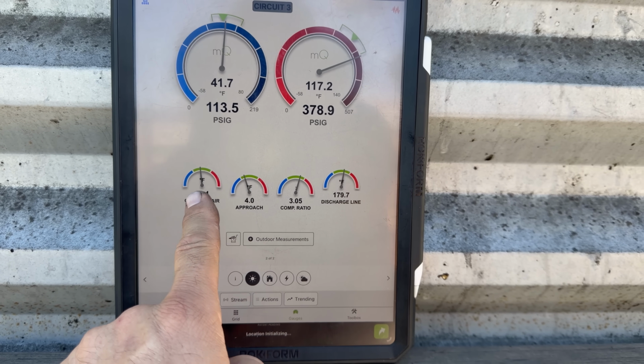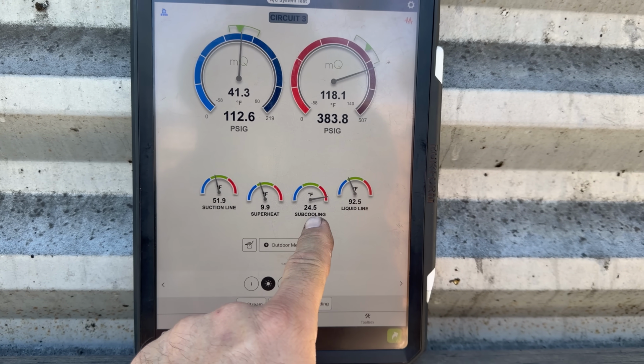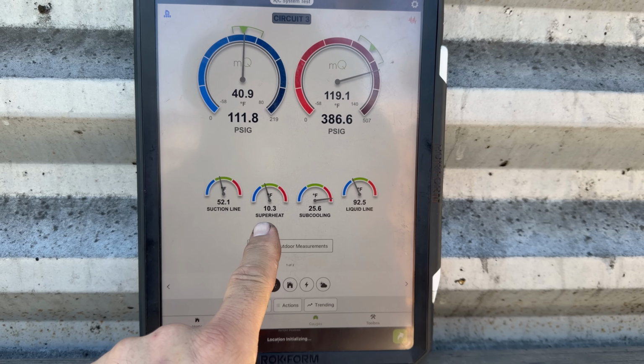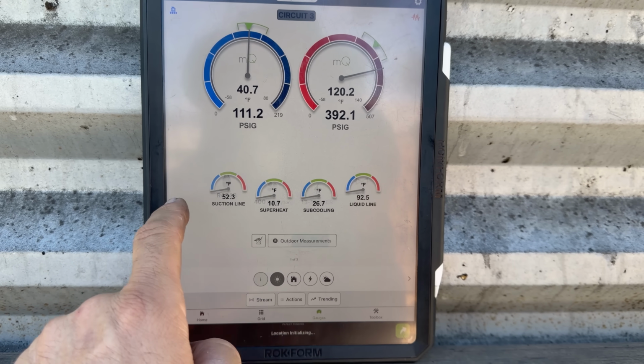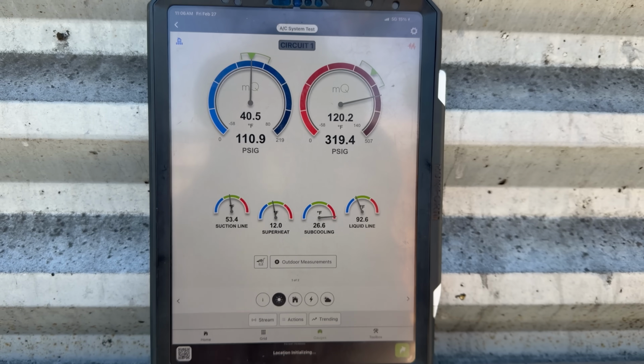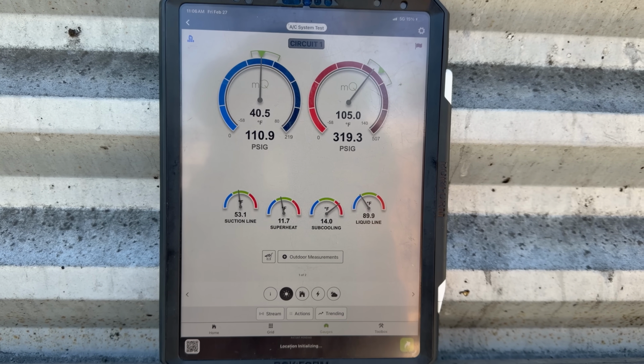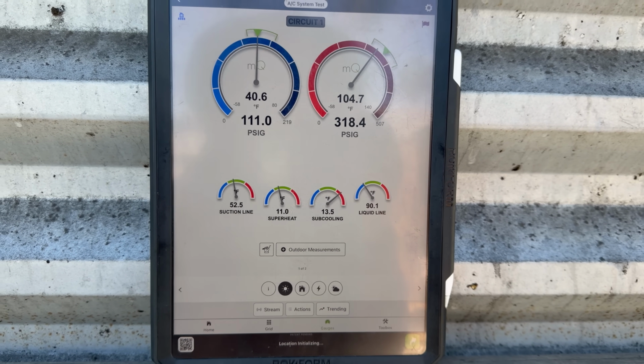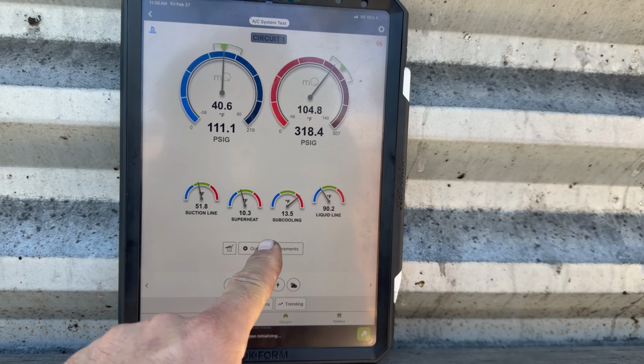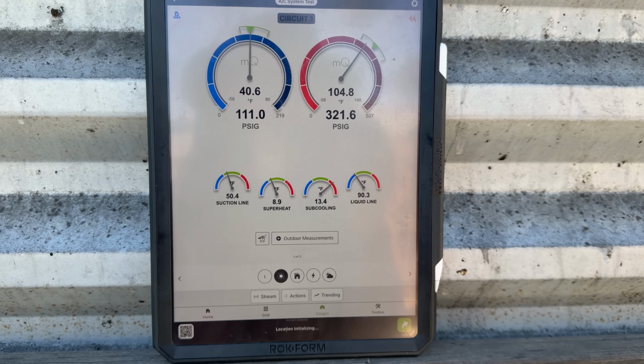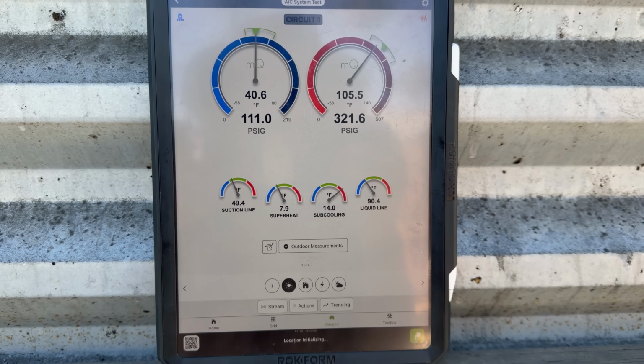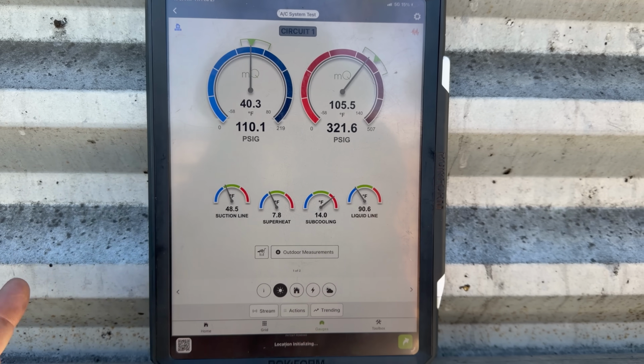Temperature split seems fine. We're now on the third stage. Subcooling's a lot higher. Superheat still maintaining. Don't see any issue there. Okay, let's go to the second stage. 14 degrees subcooling. Okay, it is kind of strange how we have such a high third stage subcooling, but that could also mean that we just need to move our air probe. But everything else looks fine.